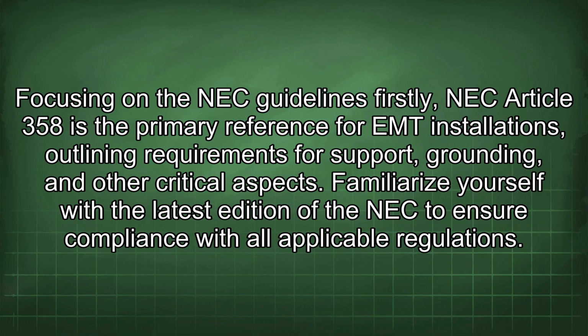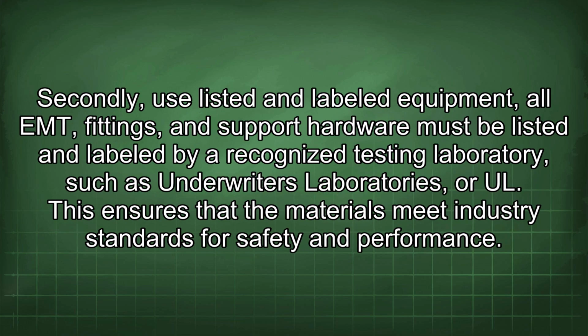Focusing on the NEC guidelines, firstly, NEC Article 358 is the primary reference for EMT installations, outlining requirements for support, grounding, and other critical aspects. Familiarize yourself with the latest edition of the NEC to ensure compliance with all applicable regulations. Secondly, use listed and labeled equipment. All fittings and support hardware must be listed and labeled by a recognized testing laboratory, such as Underwriters Laboratories, or UL. This ensures that the materials meet industry standards for safety and performance.